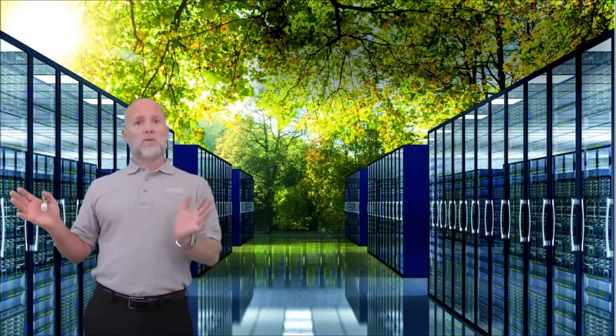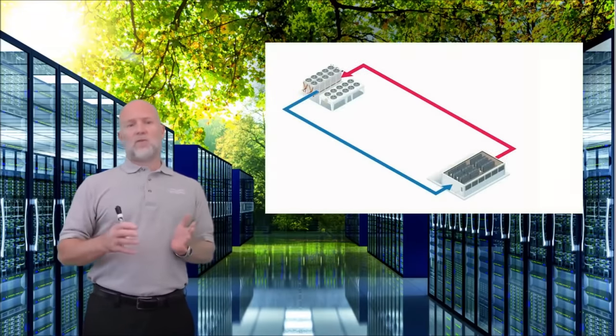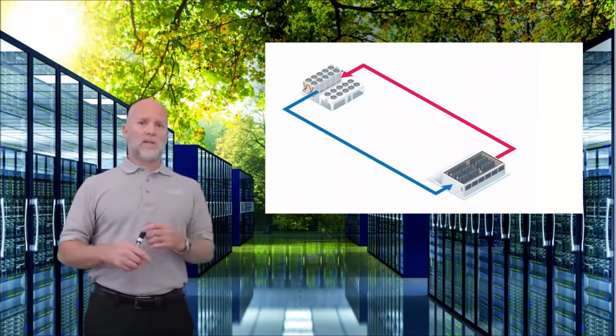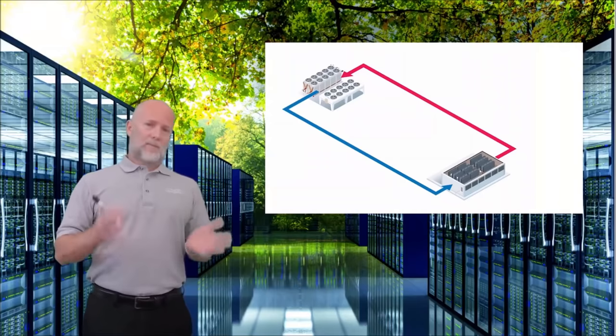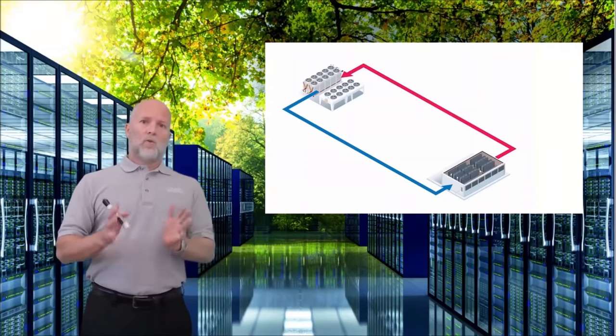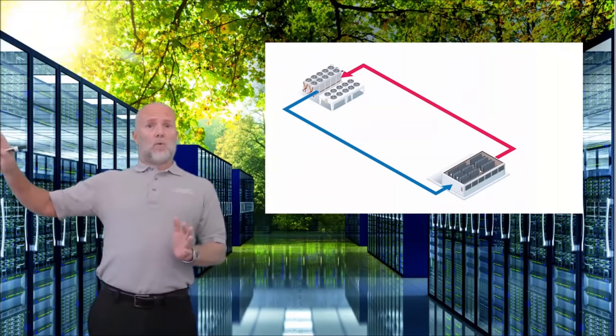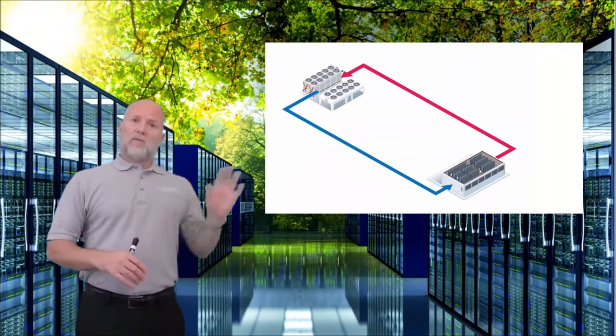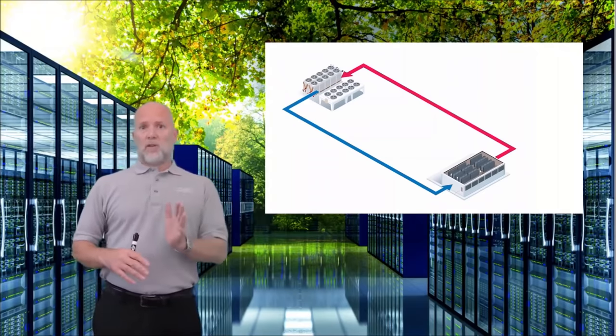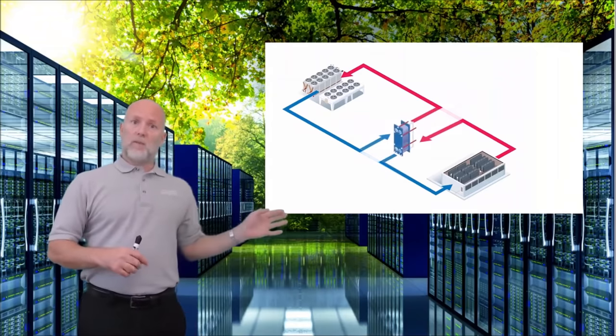The concept is that if you have an evaporative cooling tower, you have an open system that is exposed to the elements and all the contaminants in the air. In that case, it's not really a choice — it's absolutely advisable to put a heat exchanger in between your external world and your server room that acts like a shield and protects your IT equipment.